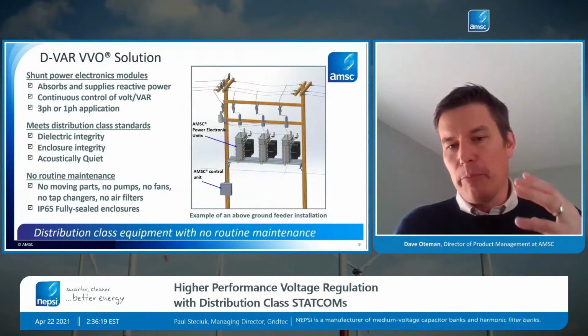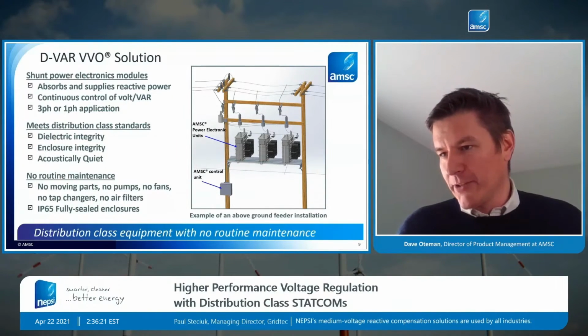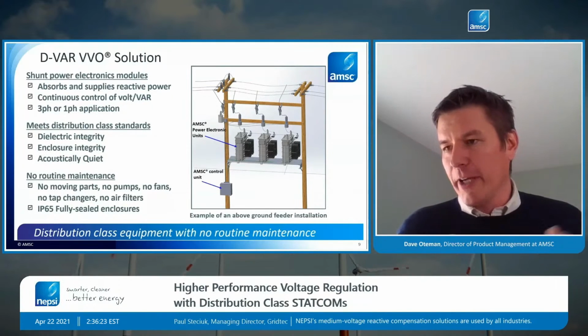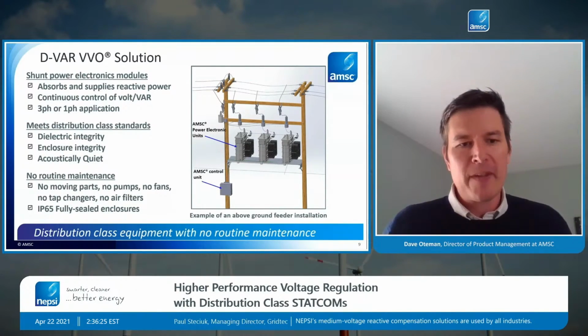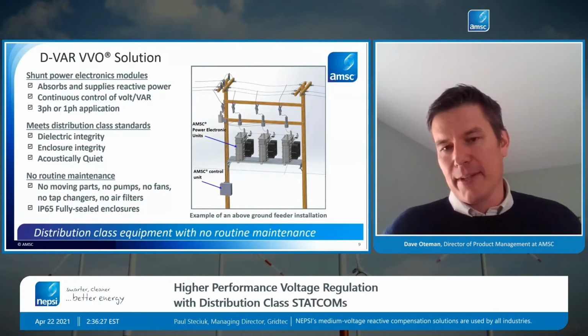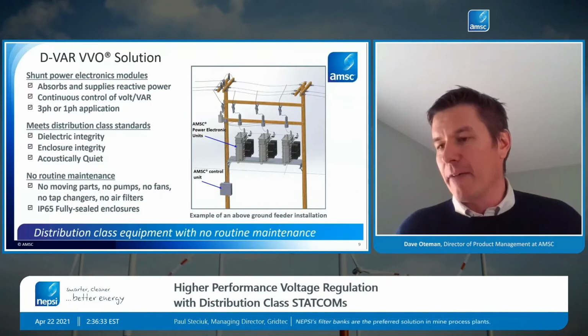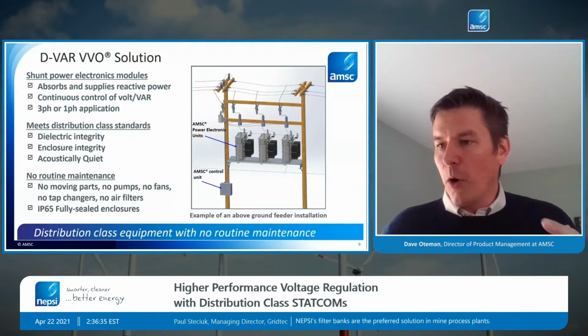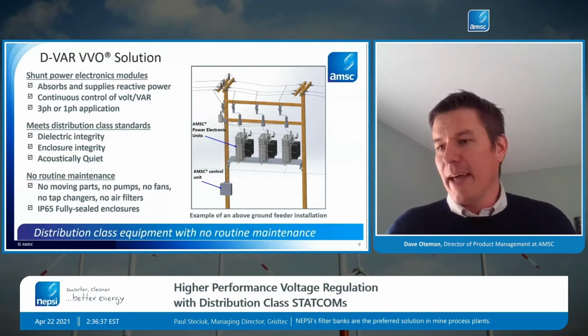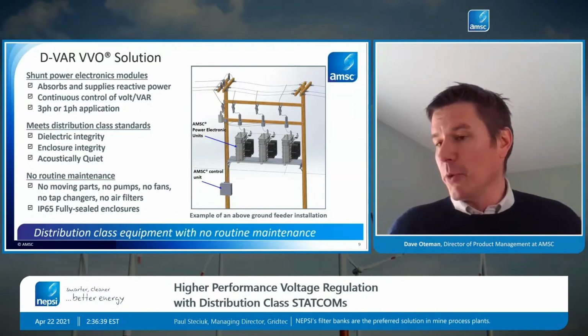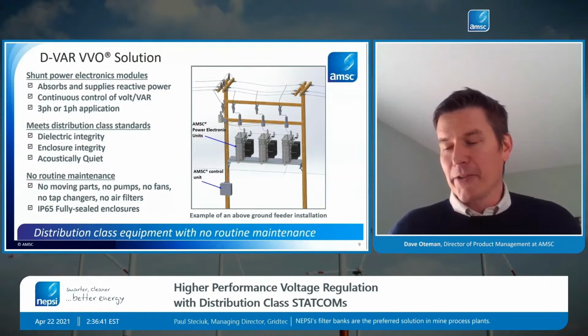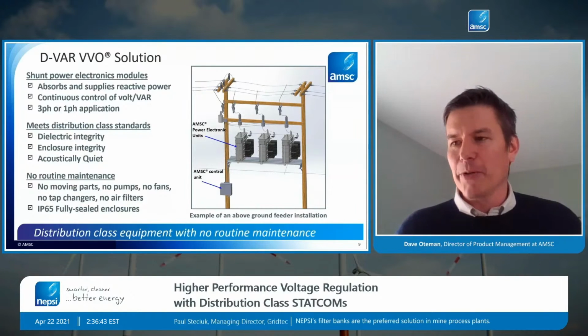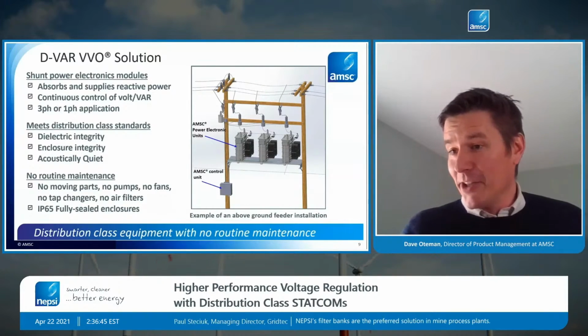So it's all based on immersion cooling, just like a transformer will naturally circulate and cool off. The same sealing system used in transformers is also used here. These are IP65 rated units, so you won't have the ingress problem that you can run into with air-cooled equipment.